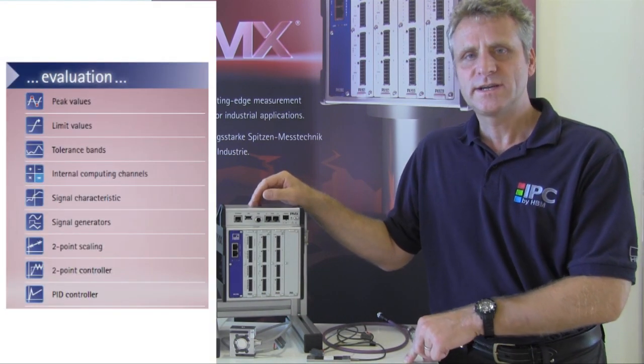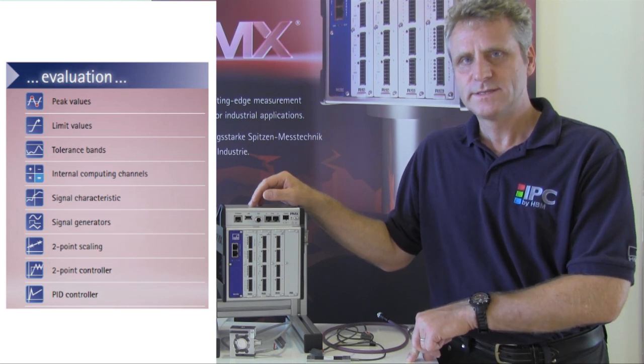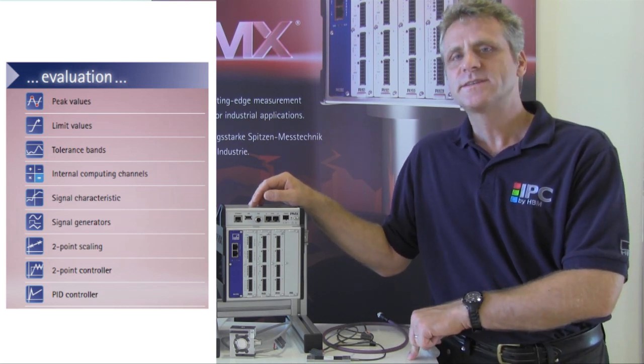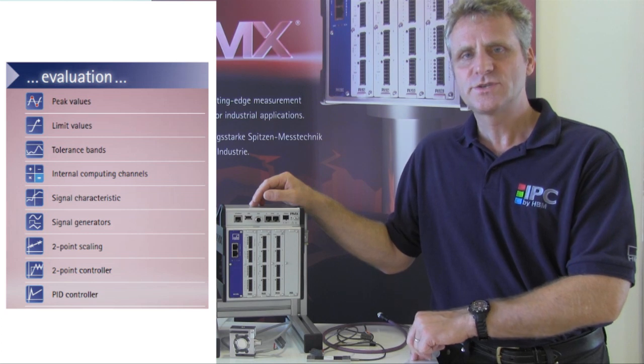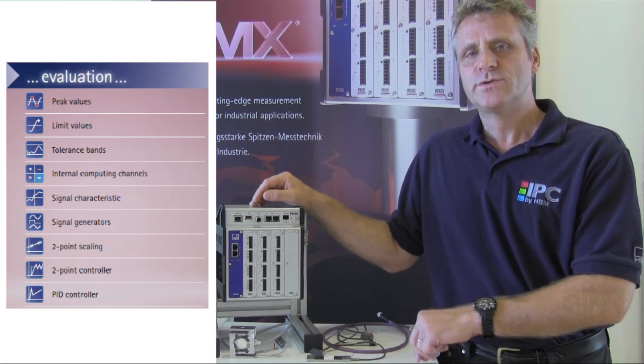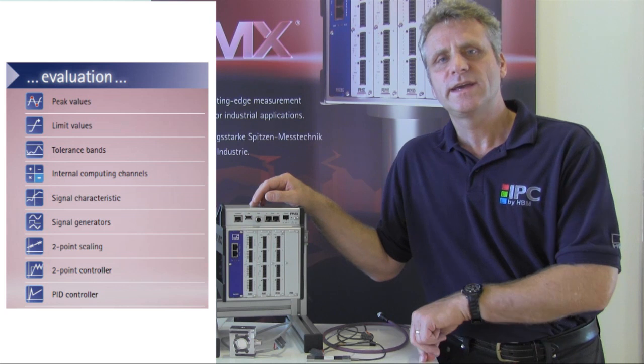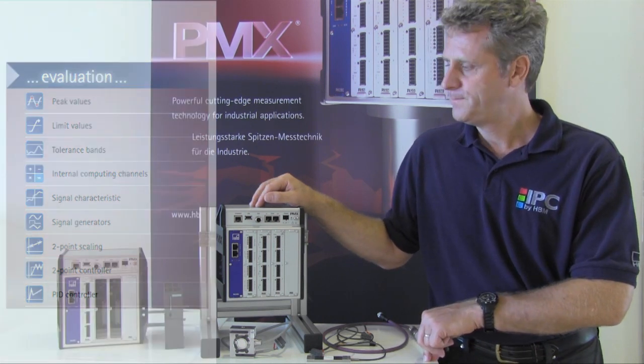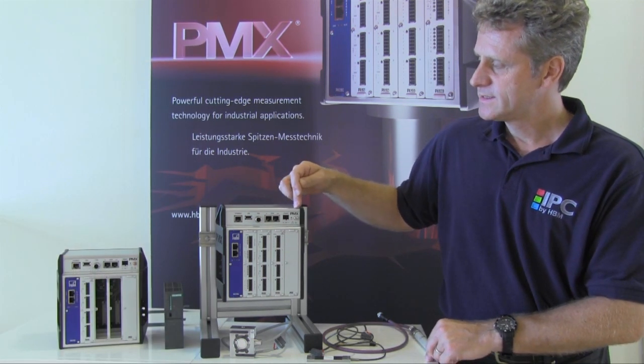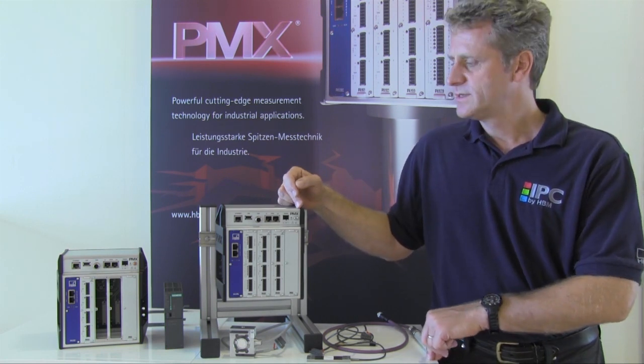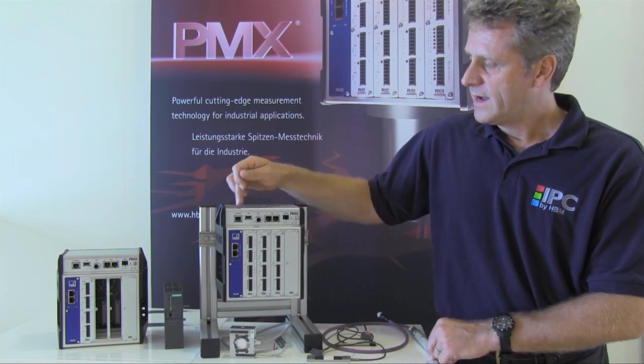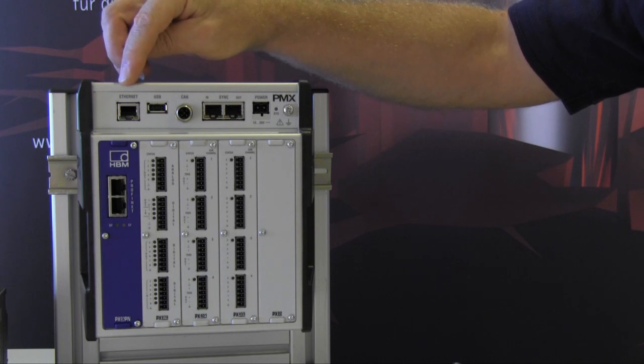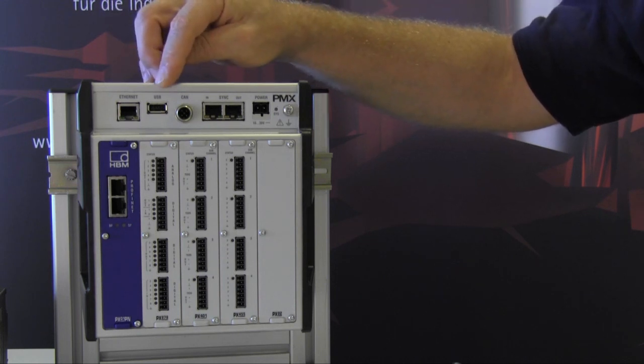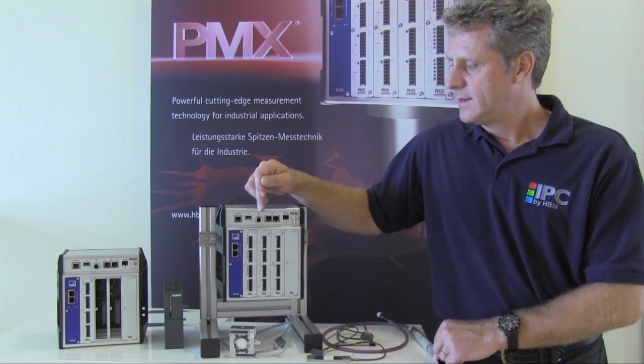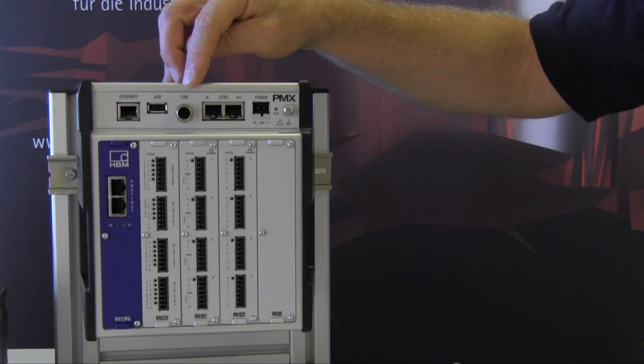A very powerful high-performance computer core works in the device itself. This allows us to equip PMX with a total of 32 calculation channels that are available for math and controller functions, peak value detection, and other similar tasks. Various connector sockets are available on the top of the device. We have the Ethernet connection for operator terminals, a USB connection for additional backup and data storage functions, and an optional CAN connection where CAN sensors or CAN field modules can be connected later.